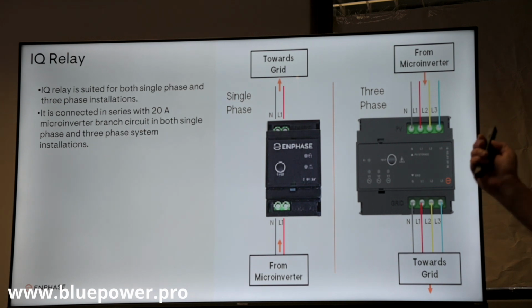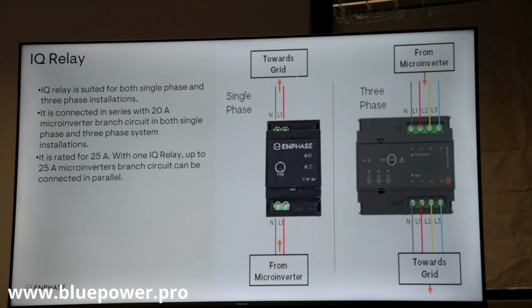20 amps, 25 amps. So connected in series with a 20 amp microinverter branch circuit, as we said, the IQ8Cs, you can use 10 of them. The IQ8Ps, which is a higher wattage product, you can only connect 8 of them to make sure that you stay within the limits of the rating of the relays. So that's on single phase.